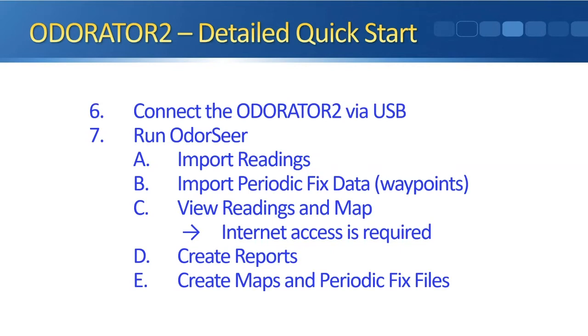But typically, reconnect the instrument, run OdorSeer, log in for permissions. You have to bring the data in, of course, and there's a couple of options to do that, but primarily bring the data into the instrument, both the readings and the periodic fix data if enabled. And then from there, view and interpret the data, create maps, select readings, etc., to create reports, and also create optionally a periodic fix file.